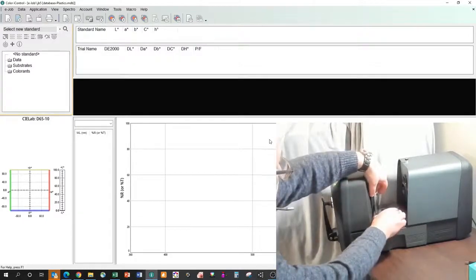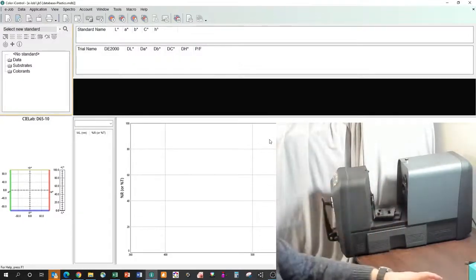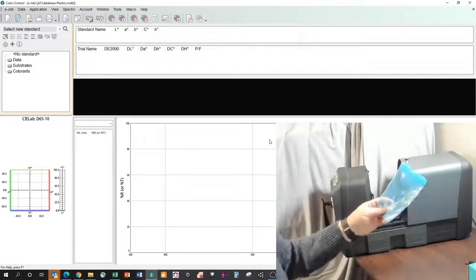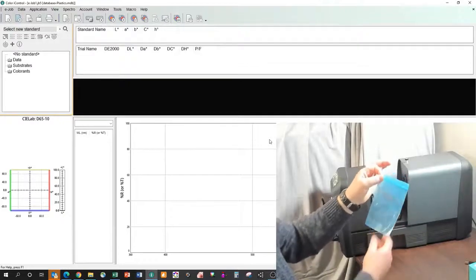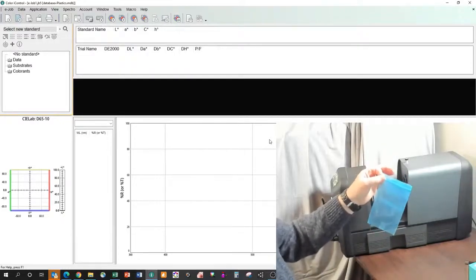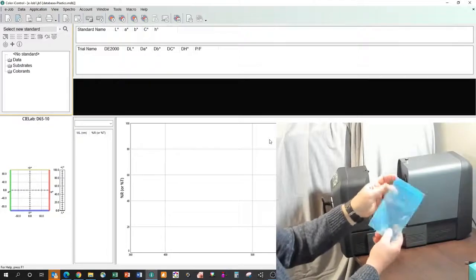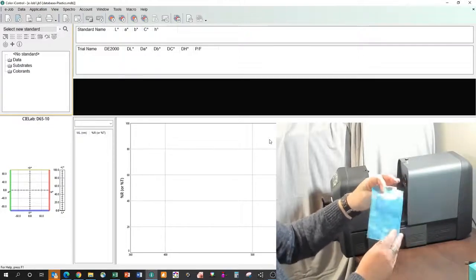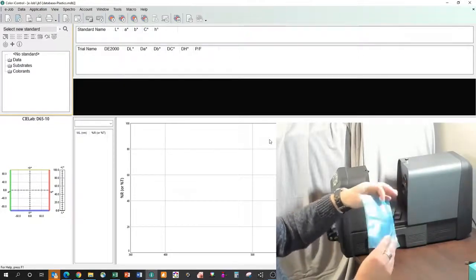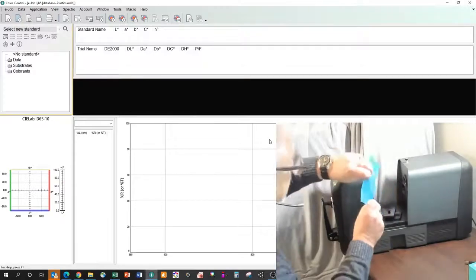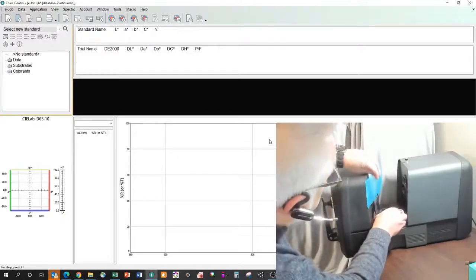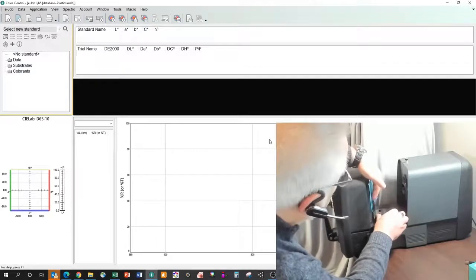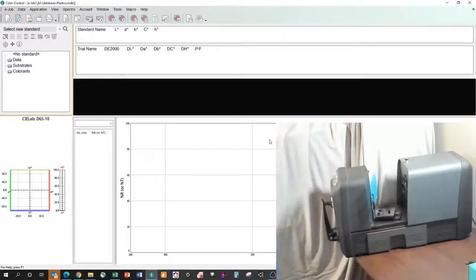So I'm going to open the clamp up, take that black plastic out, and I've got two different samples I'm going to measure just to give you some examples of how this might work. First is literally the blue plastic bag. It's from the sample kit, the transmission kit that one of the aperture plates was in. It's got a light bluish tint to it and is similar to something you might want to measure. And so of course, if I'm going to do that, I'm simply going to put this in place, let it hold it in place like that.